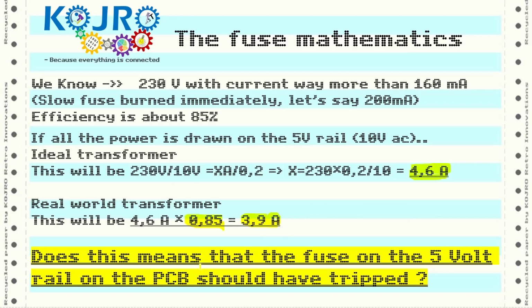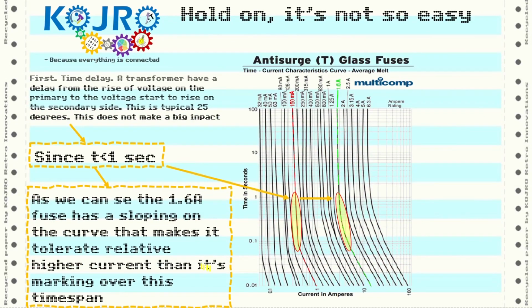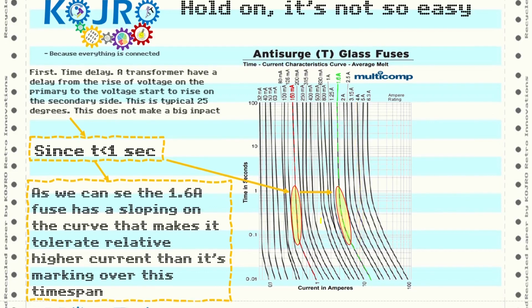Yes, it should have tripped. If we compare the two fuses, you'll see this 1.6 ampere fuse has a bit of a different characteristic - there's more of a bend in the curve. That means on this part of the curve it will take a bit more power to trip the fuse than it normally would. But anyway, there is a dependency here: at 3.9 amps, the current draw would be about here.